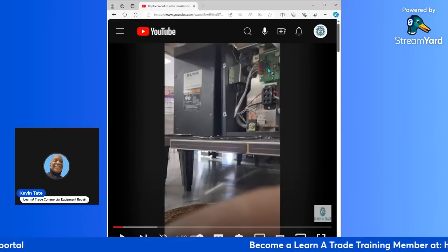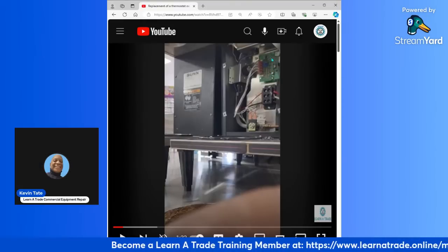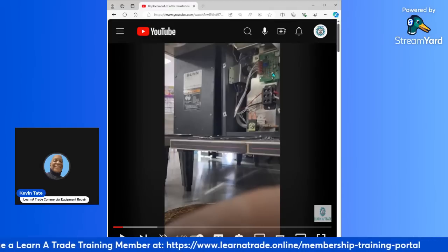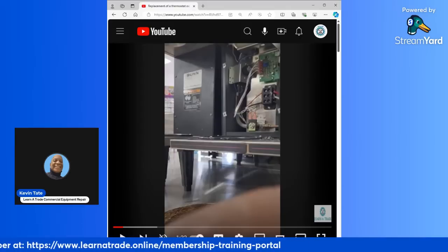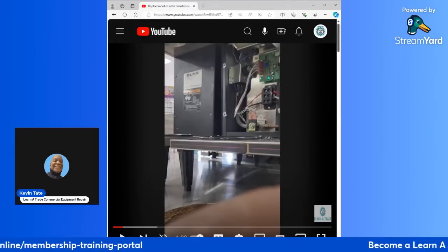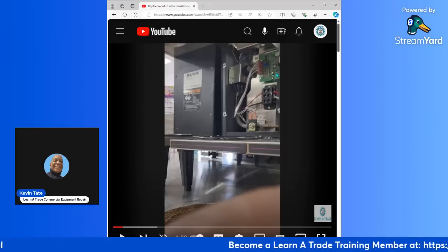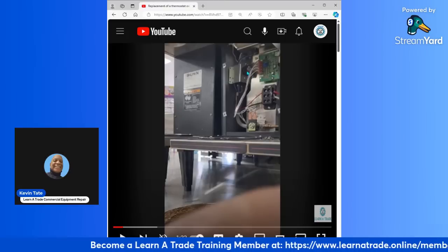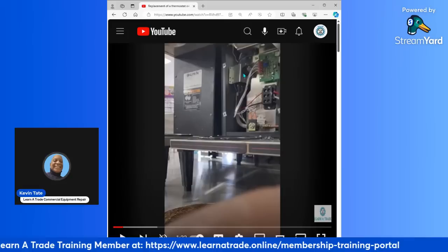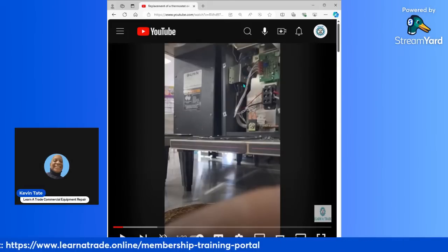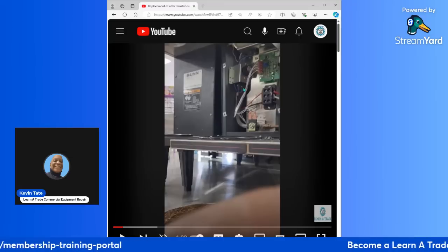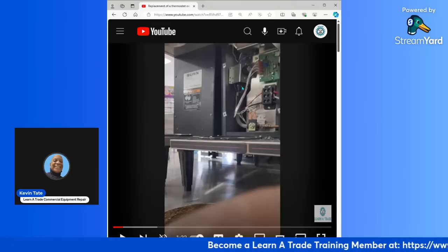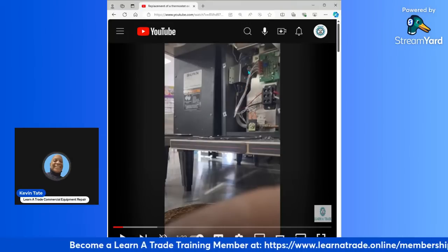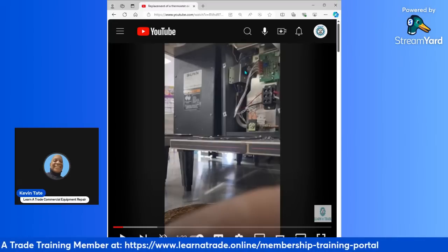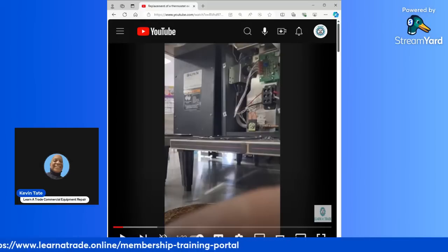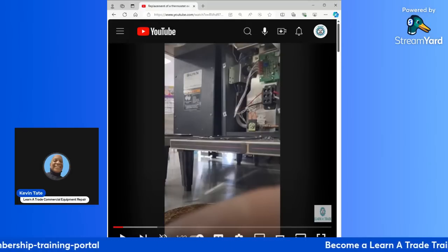Just above that, you have your digital timer. This is the timer that tells the machine when to stop a brew cycle, and you can set your calibration and everything with that. And then over here you have the actual thermostat assembly. There are two wires down on the bottom, which you will see later as I go through the process. It has an adjuster knob that you can adjust the temperature. I usually go all the way to the right and then just a hair back.